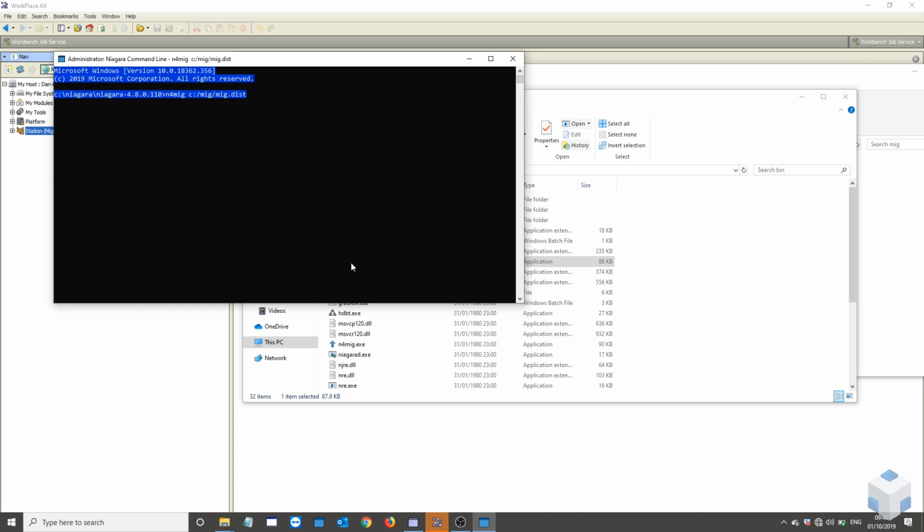Now, how quick this process takes depends on the size of your station. And again, any errors that you come across with the migration, say if you're missing a module or there's just a discrepancy somewhere, you might have to have a look around, this will actually tell us. It'll also give us the option. The command lines you could get out of the documentation, you could put extra command lines in. This is just a very quick, easy way. As I say, make sure you've always got another backup. Don't just rely on this backup for the migration, because if you've actually lost the station, you can't get another one. You're going to put yourself in a world of hurt.